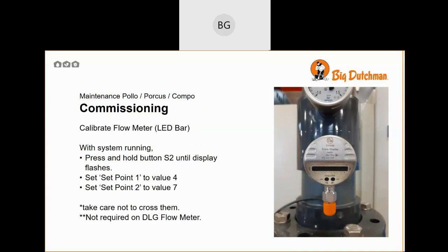Calibrating the flow meter. With the system running correctly, press and hold button S2 until the display flashes. This will tell the sensor it is now at 100%. Set point 1 to value 4 and set point 2 to value 7. This can be done by pressing button S1 and then using the 2 buttons as left and right, waiting for it to set, and then repeating with button S2. Take care not to cross the 2 set points, and this is not required on DLG flow meters fitted in Germany.